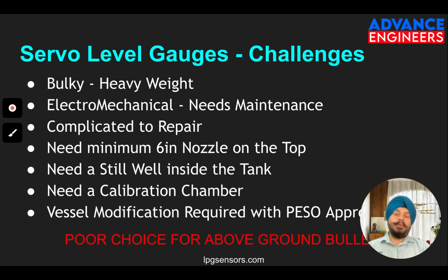It's complicated to repair because there may be hundreds of components in that, and you never know which is going to fail. It's not a small instrument, it's a big instrument. It has so many things in it: motors, pulleys, gears, sensors, Hall effect sensors, PCBs, electronics, so many things. So anything can go bad. And if it goes bad, it's very difficult to find out what the problem is, how we can find it out, where the issue is.